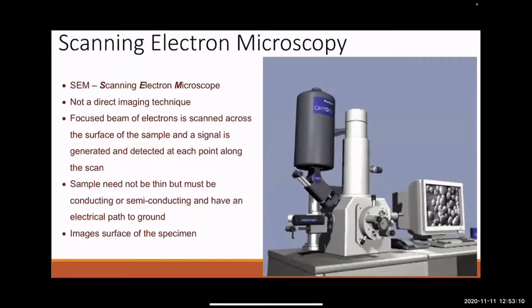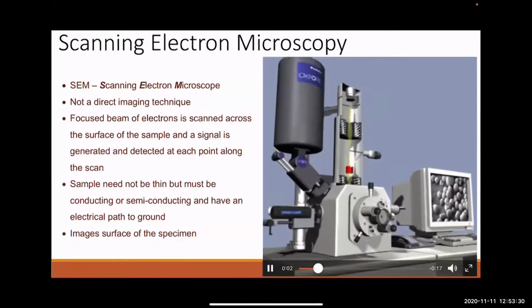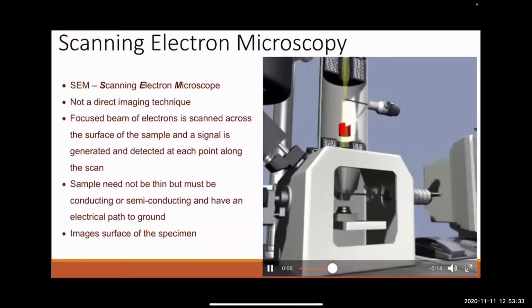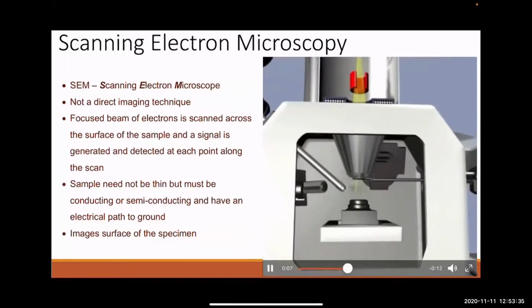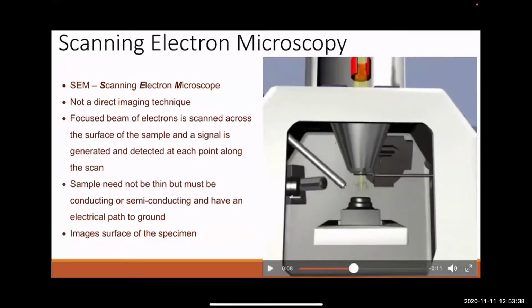What about SEM? So SEM, the operative word would be the S, scanning. And so you are taking your electron beam, and rather than trying to irradiate your sample with a parallel beam, you're actually focusing it down to a probe, kind of like the tip of a pencil. Okay, so if I play the little movie here, showing the insides of an SEM, I'm going to try and pause it maybe right here. So if you can see the little yellow trace here, this is your electron beam coming down at the tip of a pencil onto a sample that would sit here.